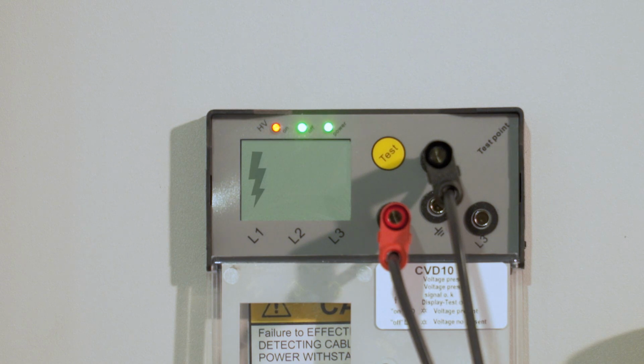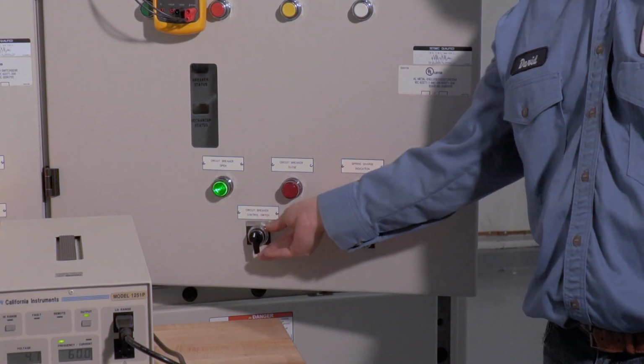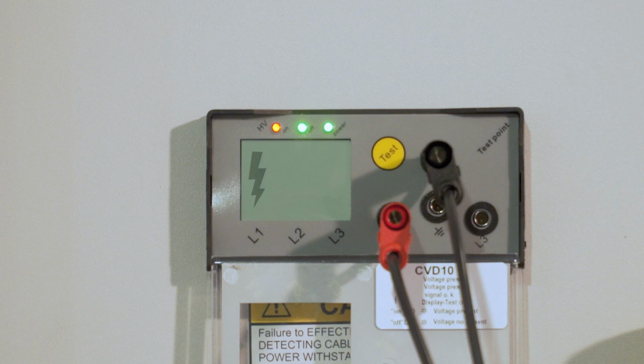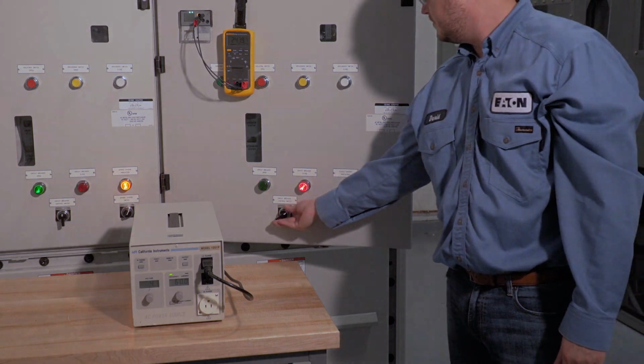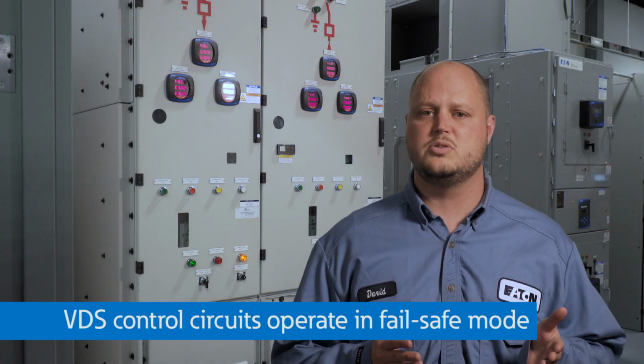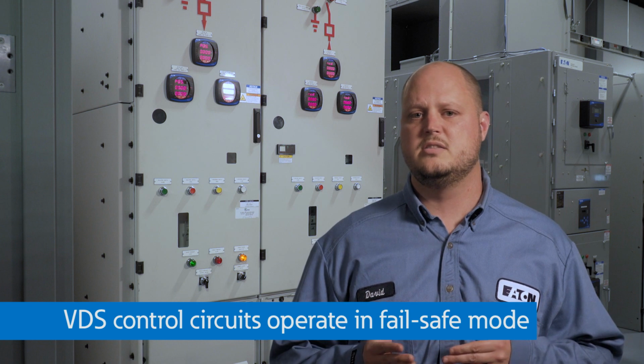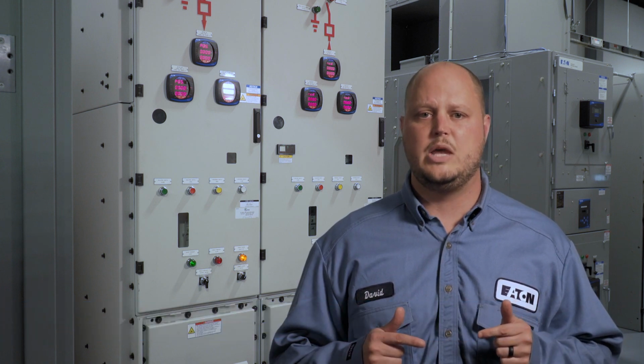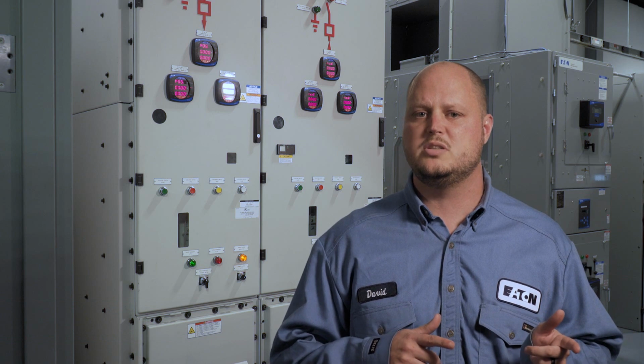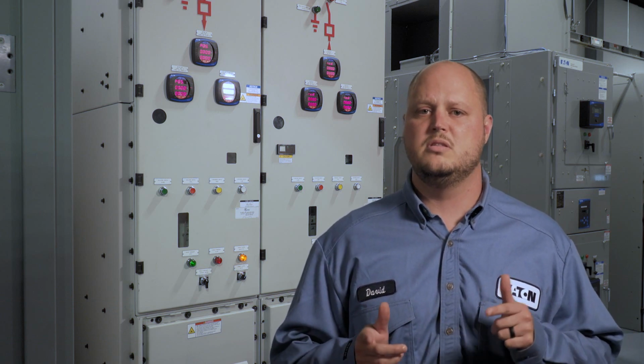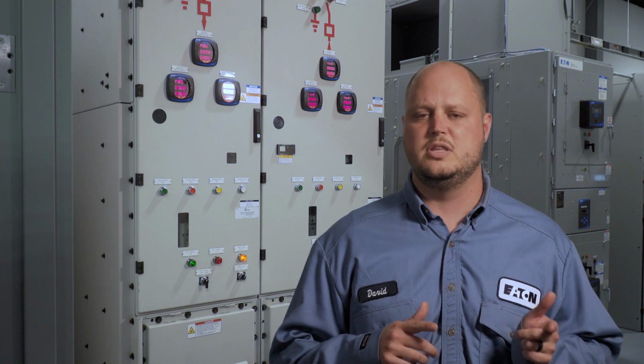You can see that the red high voltage light turns on, designating medium voltage in the cable compartment, and that I cannot close the circuit breaker. After now removing the low voltage signal, the red light designating high voltage in the cable compartment turns off. There is now no voltage in the cable compartment, and I can close the circuit breaker. Additionally, these control circuits are designed in a fail-safe manner such that if there is a VDS system failure, it would also prevent the operator from moving the earthing switch to the ground position or closing the already grounded circuit breaker onto the live cables.